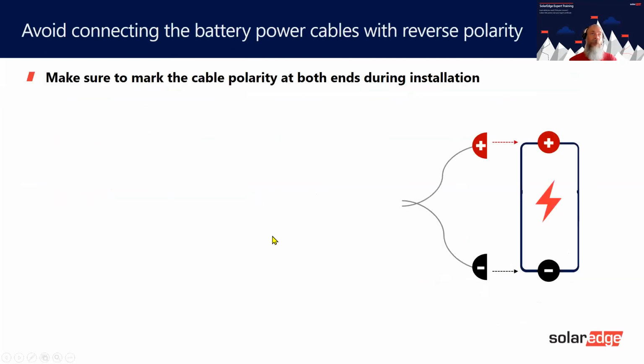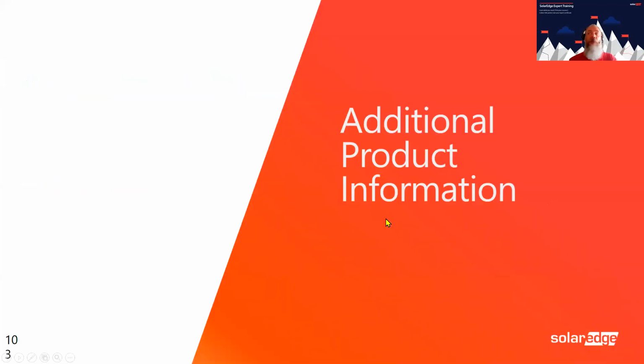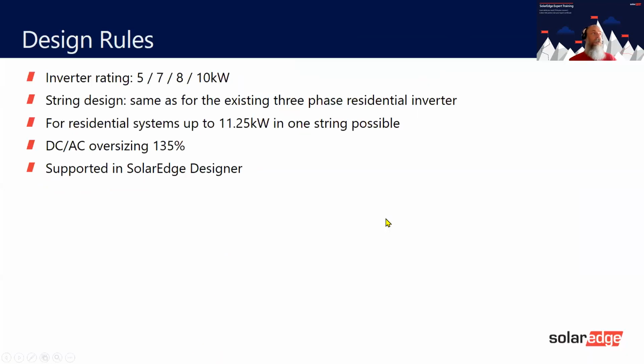And most importantly, polarity. Make sure that you mark both the same ends, because otherwise it could go a bit funny. And the last thing, design rules. The inverter is 5, 7, 8, and 10. String designs are the same as residential inverters. You're still allowed up to 11.25 kilowatt in one string, and the oversizing is 135%, and it's supported in the designer.